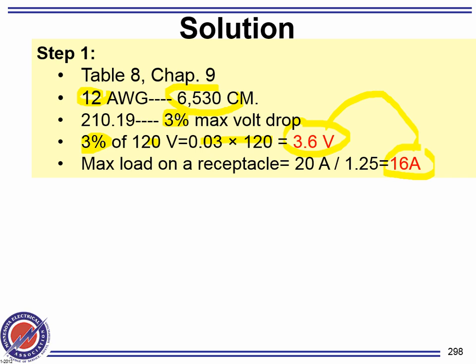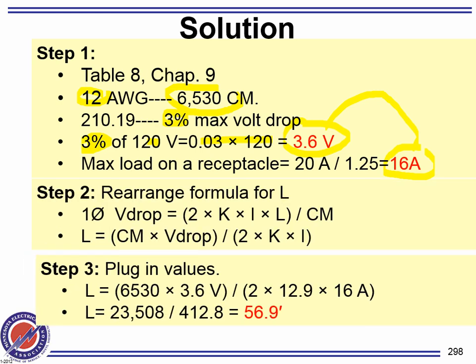All right, gentlemen. Now once you do that, you have to flip the formula. Remember how we just flipped it a second ago. Then your formula looks like this. Then start plugging. Here's your circular mill. Here's your voltage drop. Where did you get this number from? This is right from here. The 3% of 120. Here's your 2 from the formula. This is from given. Where did you get the amps from? That's from here. And gentlemen, you got this number.